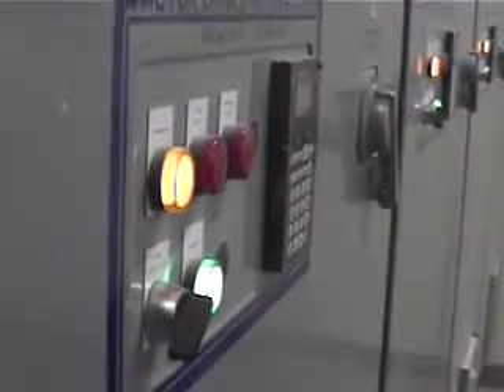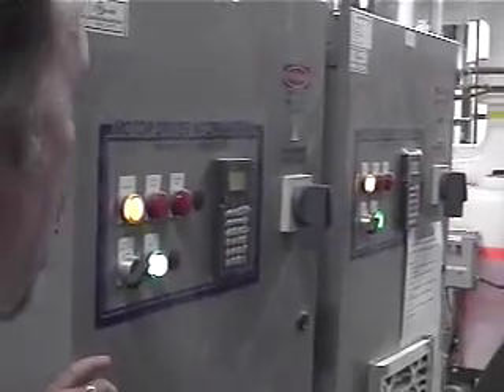VFDs for the supply fans right here. This one's your outside air fan right here. And these VFDs here are your hot water pumps, pump 5 and pump 6. Of course, these are for the building, so they also feed the heat exchanger for the coil on it. And then you've got pump 7 and 8, which are on your secondary side of that heat exchanger. They're constant speed. Yeah, they come out of the MCC. So these just disconnect power between the MCC and the motor.